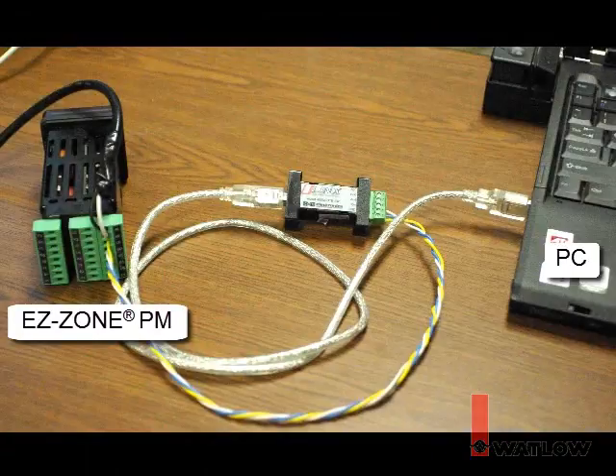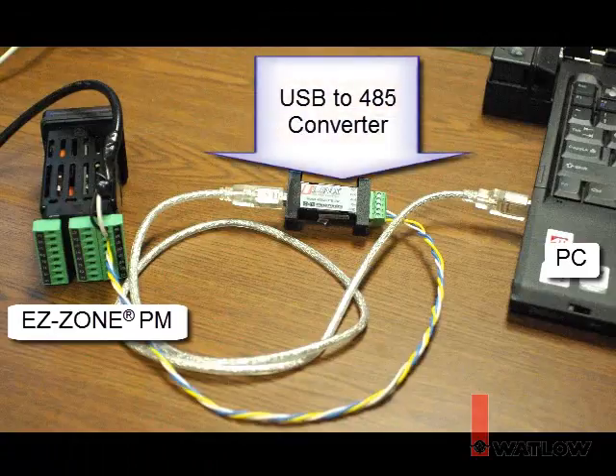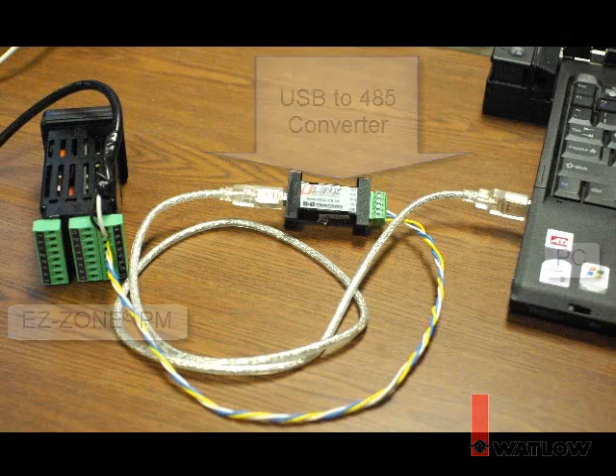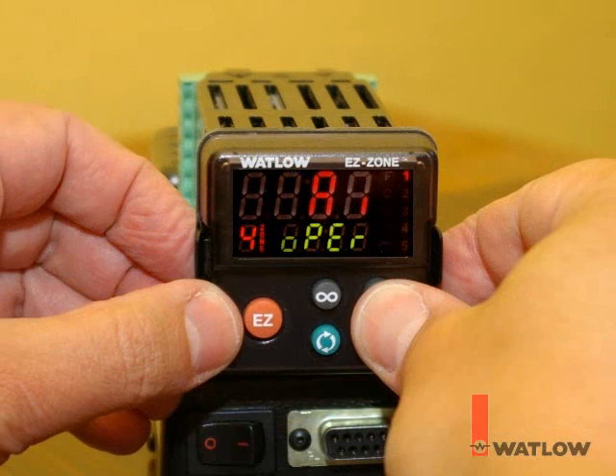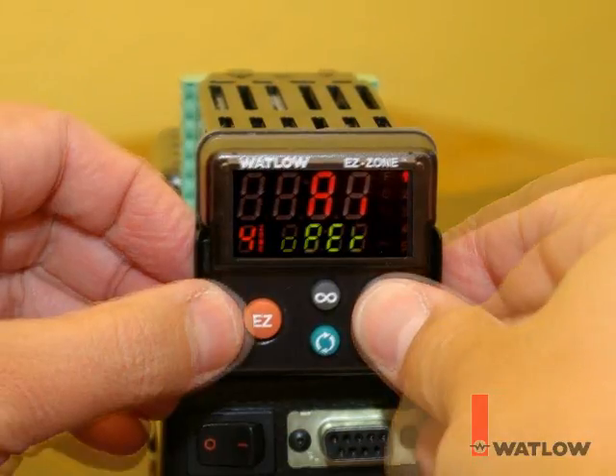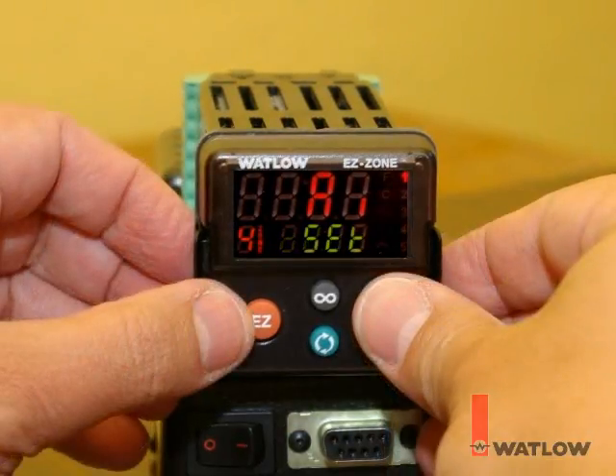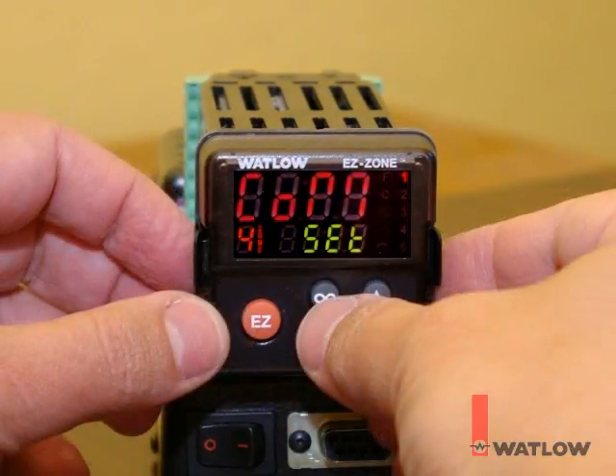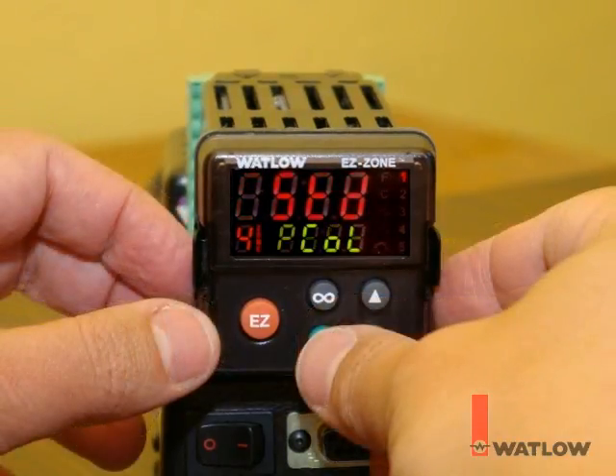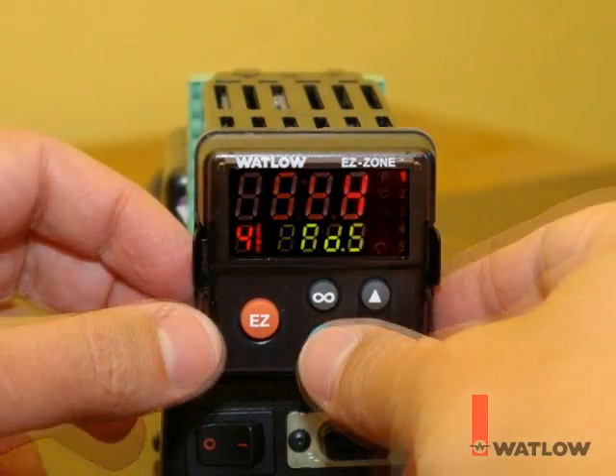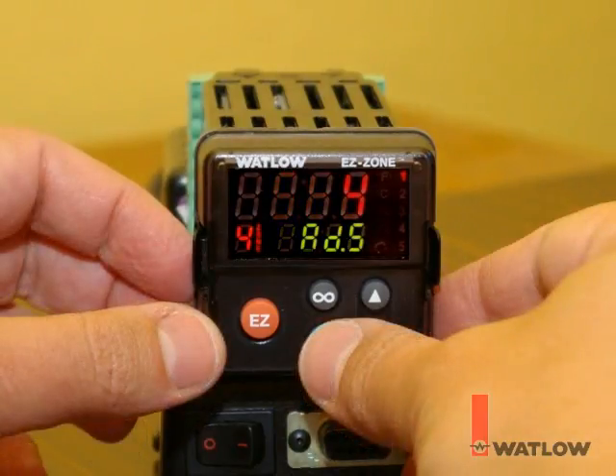In this session, the computer is connected to an EZ-ZONE PM controller via a USB to 485 converter. The converter has been installed as a serial port named COM 6. Like all EZ-ZONE products, the PM supports the standard bus communications protocol. This model also supports Modbus RTU, so on the Setup Page's Communications menu, I've made sure the protocol is set to standard bus. Also, the PM standard bus address or zone number is 4.